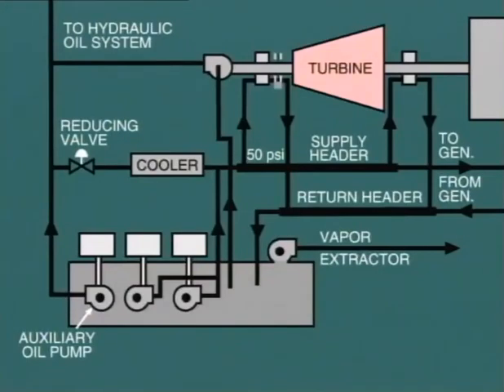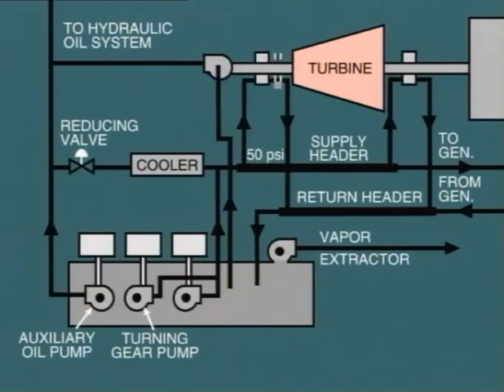When the turbine is out of service and operating on turning gear, we still need to provide lubrication to the bearings. However, in this situation, with hydraulic oil not required, it would be inefficient to run the large auxiliary oil pump. Instead, a small pump is installed, known as the turning gear oil pump, and this provides sufficient oil for lubrication only.